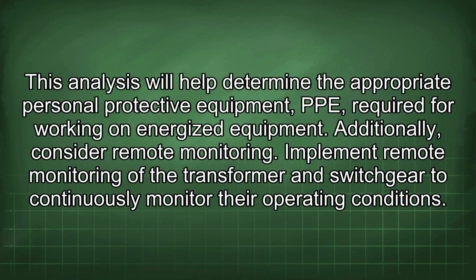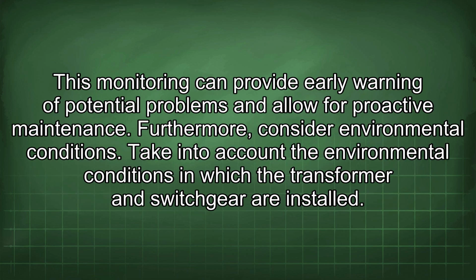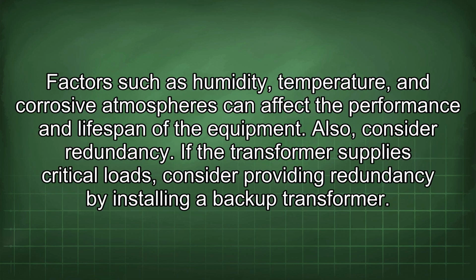Implement remote monitoring of the transformer and switchgear to continuously monitor their operating conditions. This monitoring can provide early warning of potential problems and allow for proactive maintenance. Furthermore, consider environmental conditions. Take into account the environmental conditions in which the transformer and switchgear are installed. Factors such as humidity, temperature, and corrosive atmospheres can affect the performance and lifespan of the equipment.